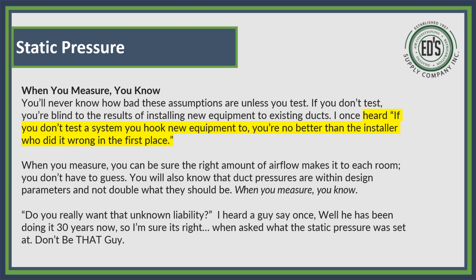When you measure, you can be assured the right amount of airflow makes it to each room. You don't have to guess. You will also know that duct pressures are within design parameters and not double what they should be. When you measure, you know. Do you really want the unknown liability?